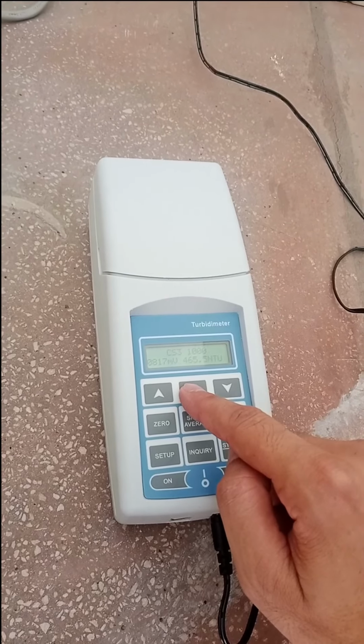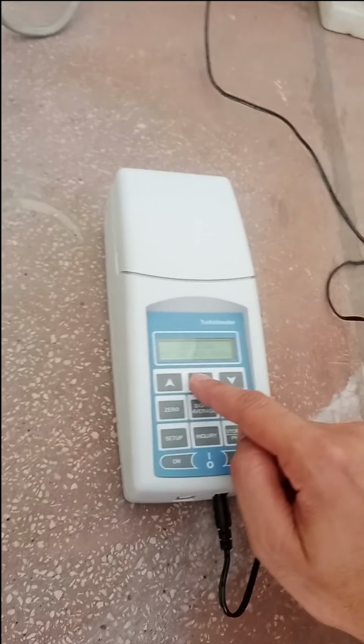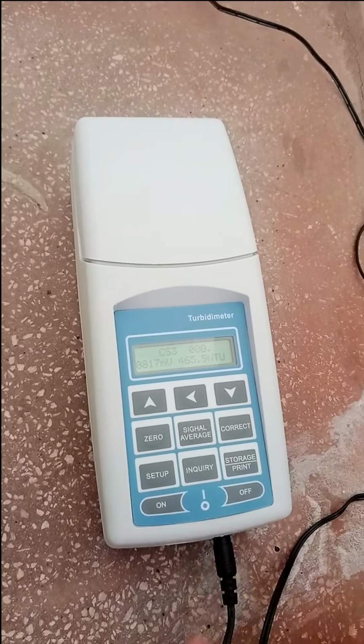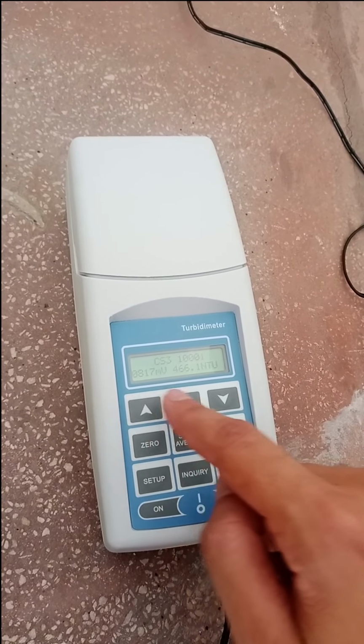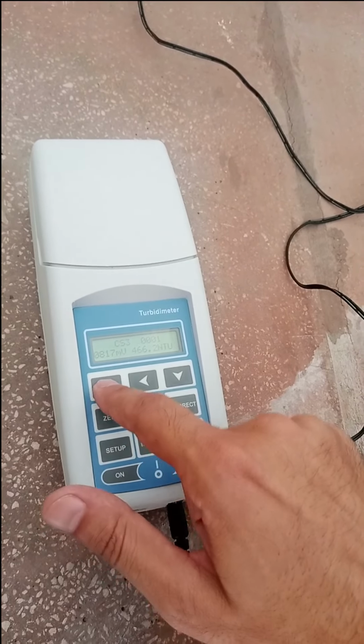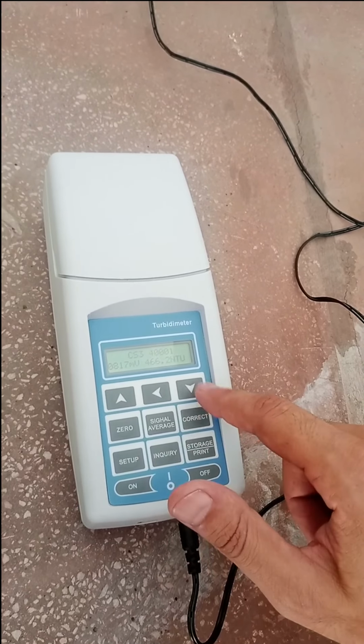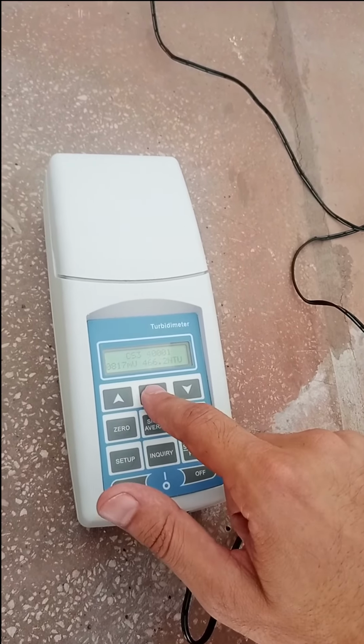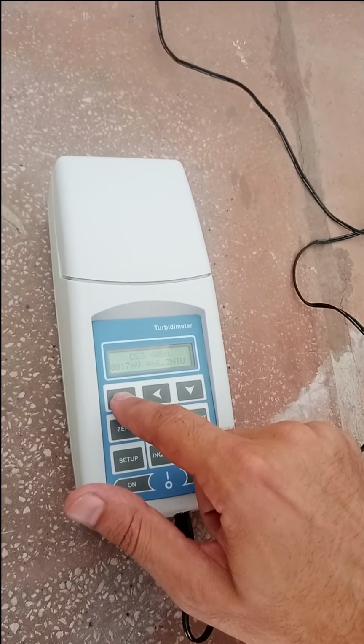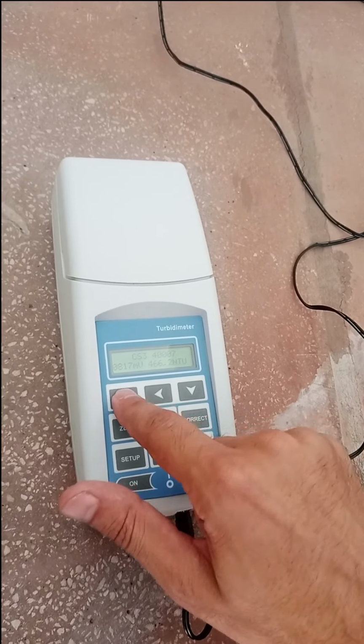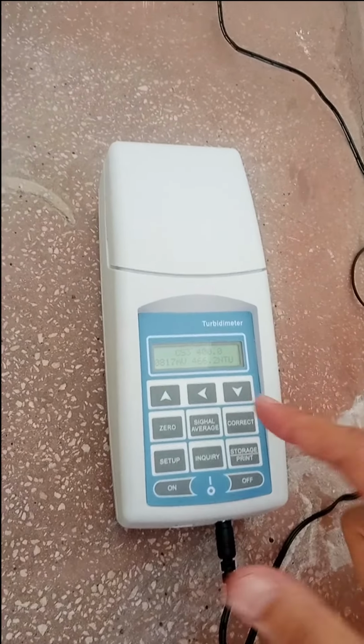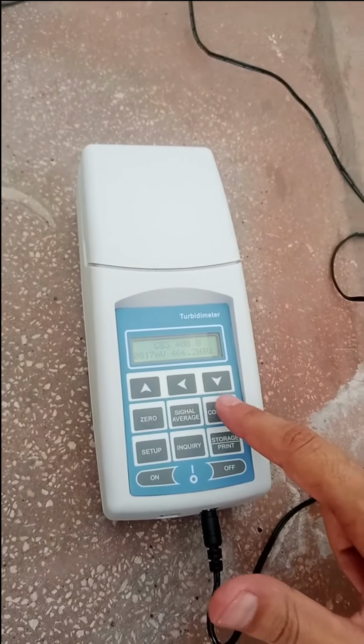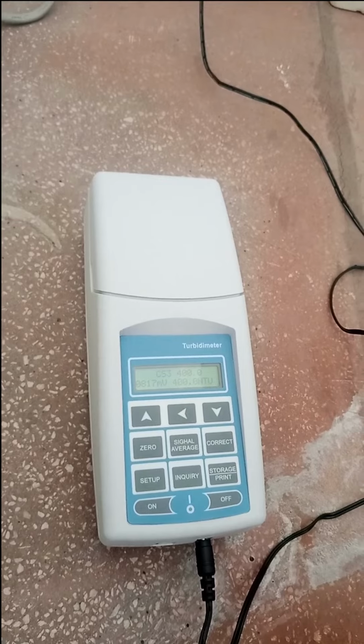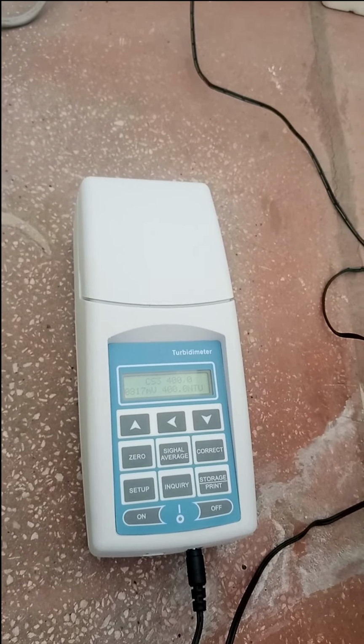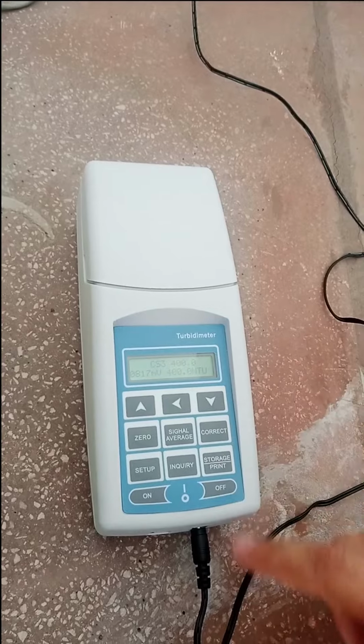First we have to make it 400, right? So make it 400 because our reference calibrated sample is 400. Now it is 400, but the value it gives is 466.2. So now we will press the correct button, since the actual value of the sample is 400 NTU. So now it's calibrated and it will give us values in reference to this 400 NTU sample. So calibration completed.